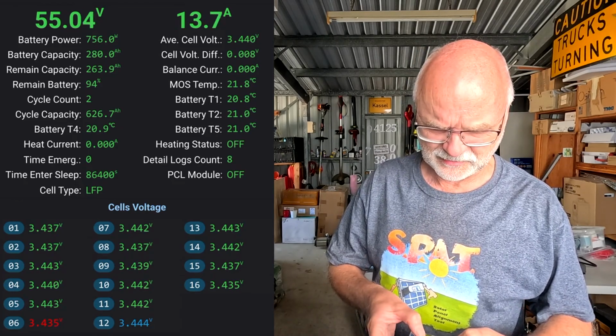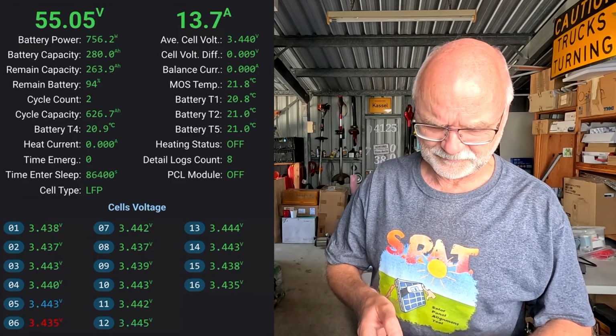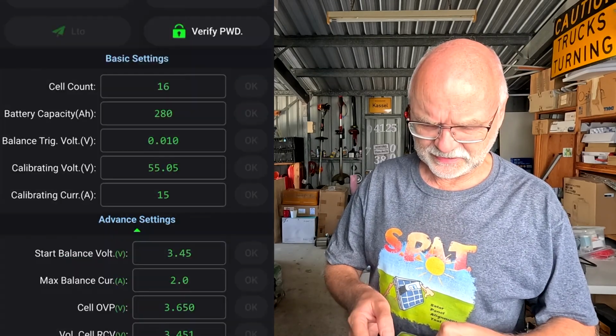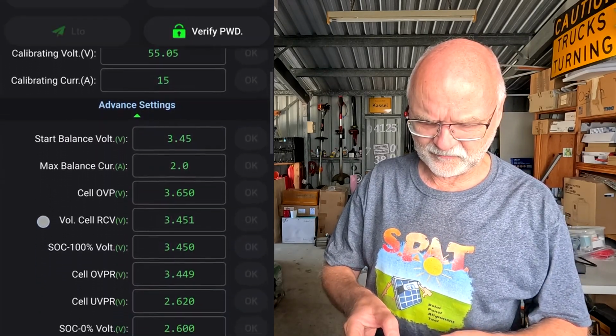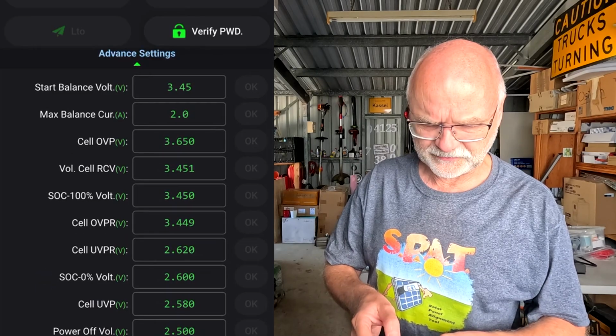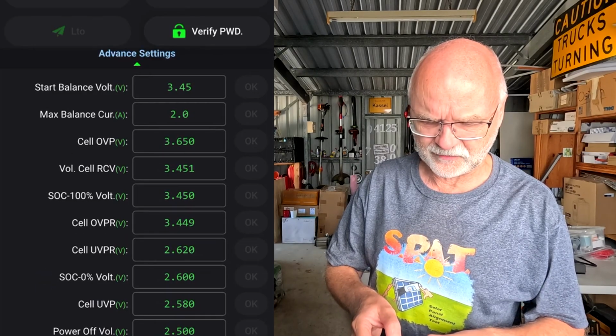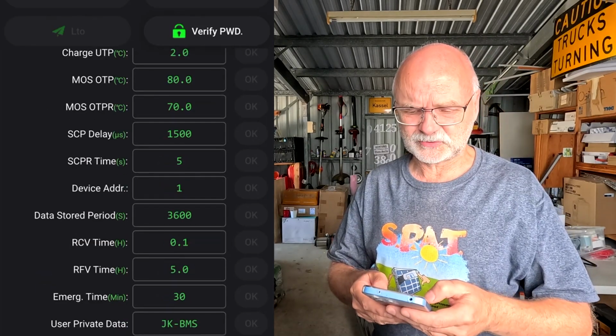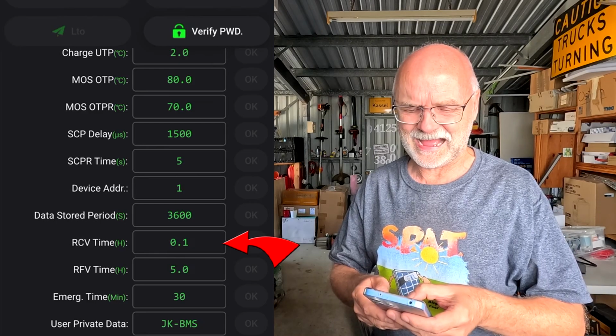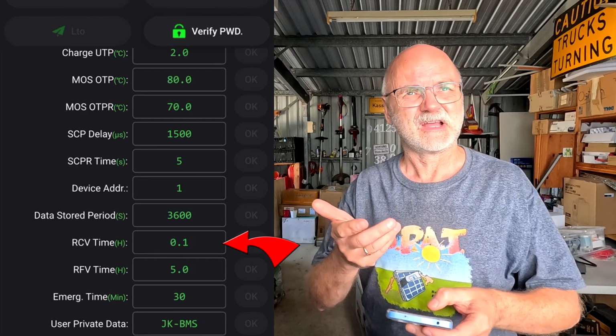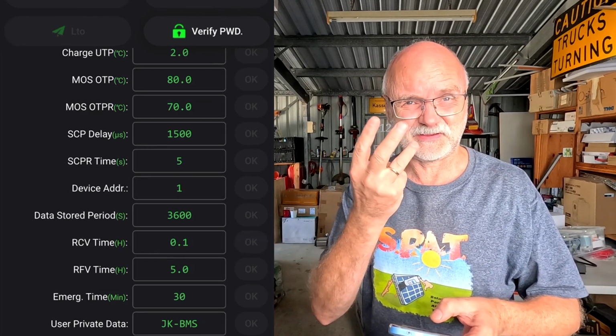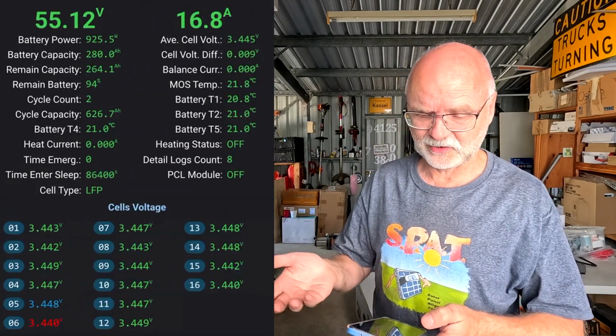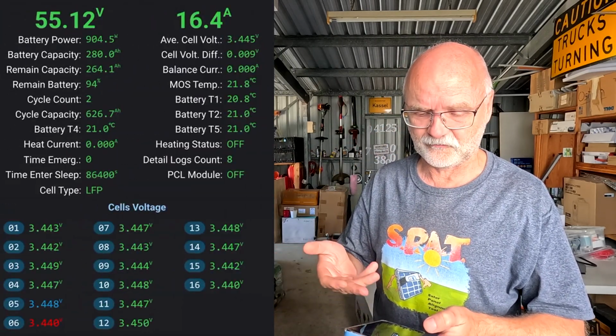3.4, what's the highest? 3.44 volts. Okay, quickly checking the settings here. 3.45 balance start voltage, requested charge voltage 3.451. And I've set the absorption timer to 0.1 hours, which is 6 minutes. So we just need to wait until we reach 3.451 volts, and then the timer starts.